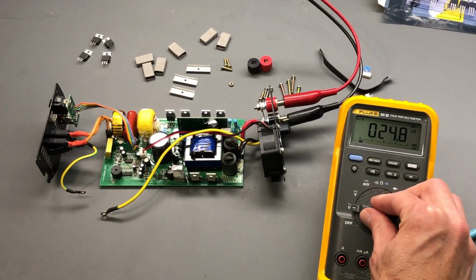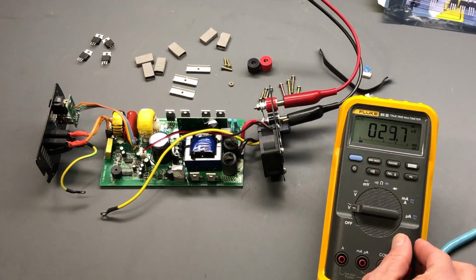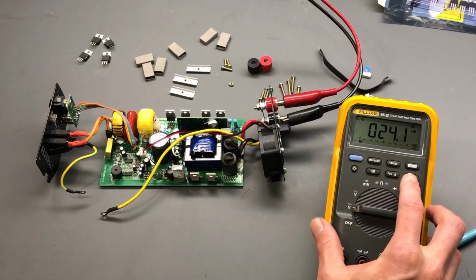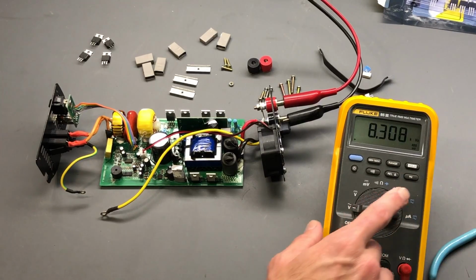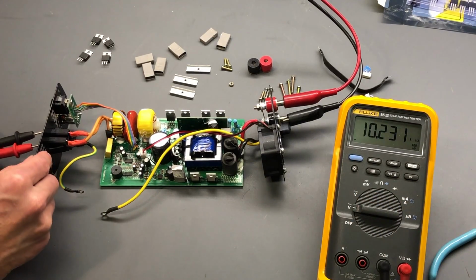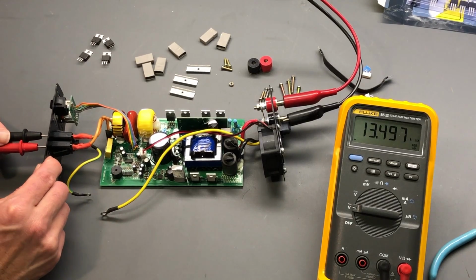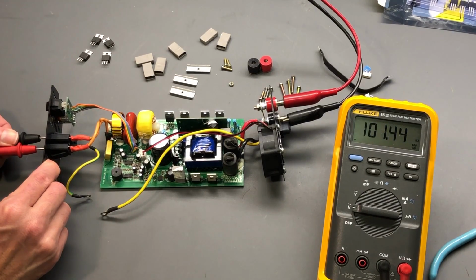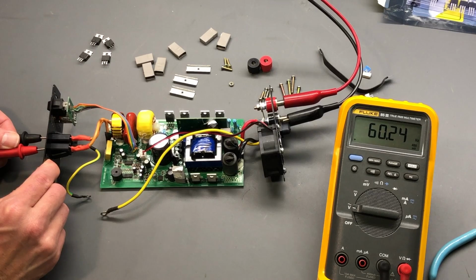Let's take a look at the frequency on the output. Should be 60 hertz or very close to that. So we'll set this to frequency, take a look here. Yeah, that looks very good, 60.24 hertz. So again, 60 would be ideal, and 60.24, nothing wrong with that.